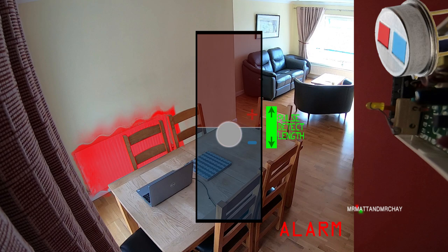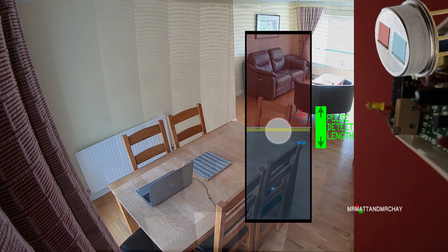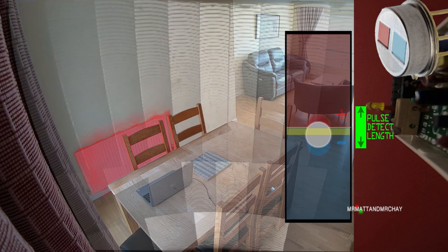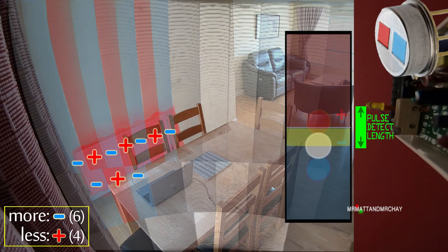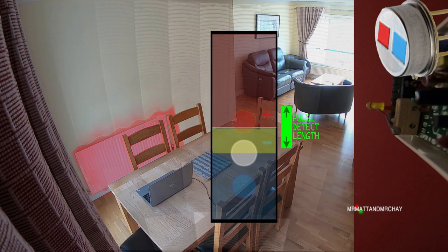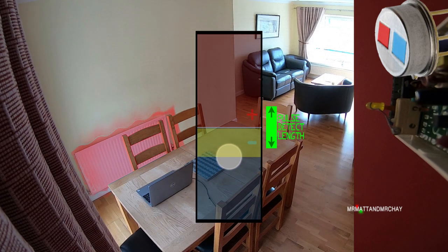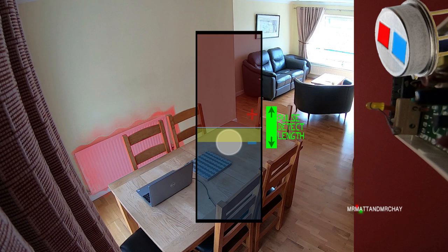The PIR lens may aim the positive and negative elements from the pyroelectric sensor into slightly different areas of the room. If the readings from these elements were to imbalance, this may actually give a high average reading, but a pulse is not achieved because gradual rises and falls, like from this radiator, are disregarded. Any new average reading is then learnt as the new base level for detecting pulses.